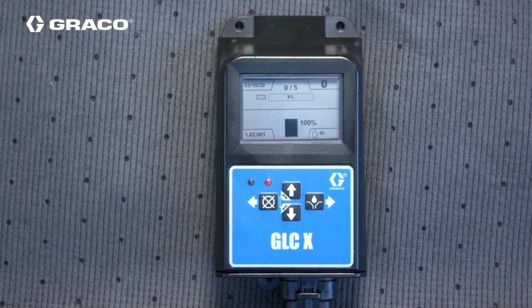Alternatively, the machine count feature can be used together with the interval time either to trigger an alarm if the time expires or run the pump when the time expires, which is sometimes called a backup time. Note, one exception is in the case of G3 grease pumps. If your application requires a G3 grease pump with the paddle mode for the low-level switch, then machine count is unavailable because that input is already being used by the low-level paddle.